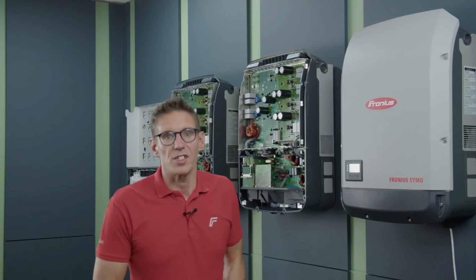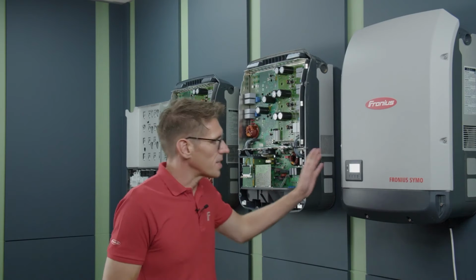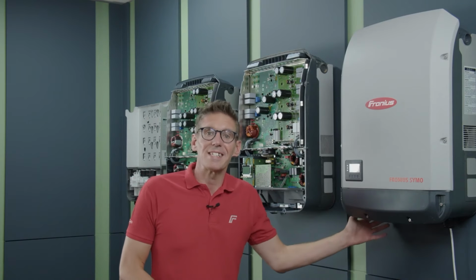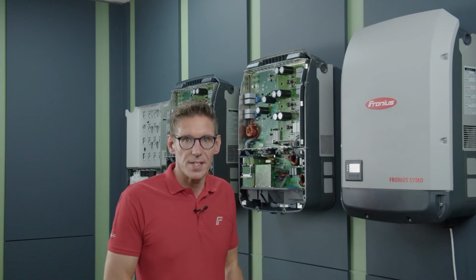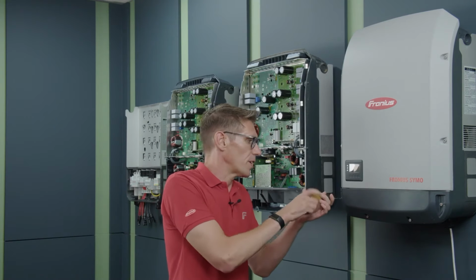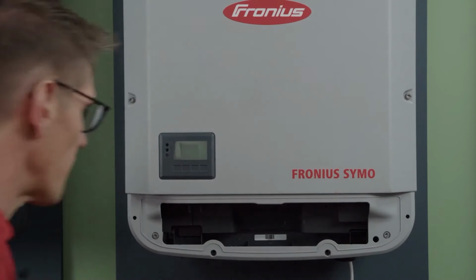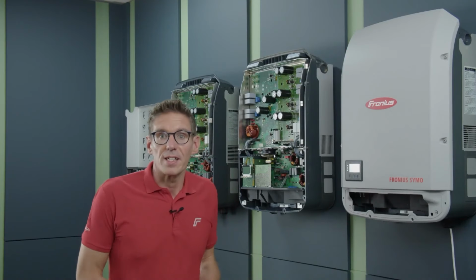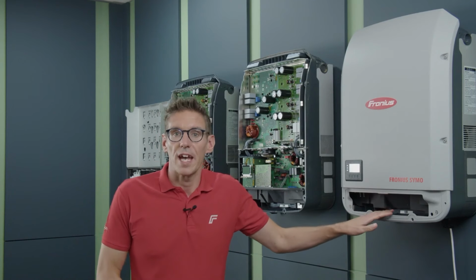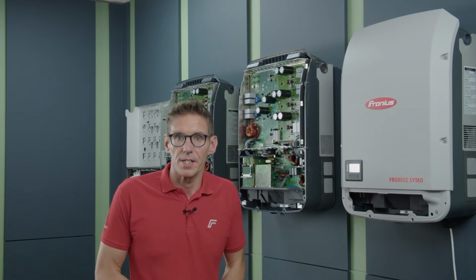Once you've received your Exchange inverter, you can go to site and replace the units. Go to the existing inverter and make sure that the DC and the AC are both isolated. You can then unscrew the DATCOM cover. There are 4 fasteners for this. Remove the cover. You may find that some devices will have Cat5 cables for data communications. If so, you'll need to remove those from the device.